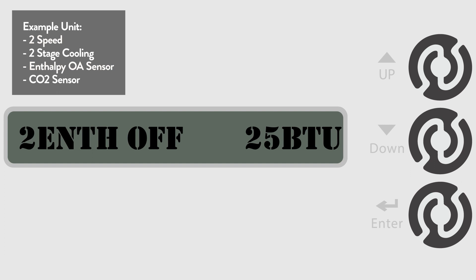The next several screens deal with CO2 sensors. In the 5 configuration state, we told the controller we had a CO2 sensor and we set the sensor voltage. These next adjustments will set the minimum and maximum damper position settings for the controller when not in free cooling. These settings are made by adjusting the voltage to the economizer actuator. Since we have a 2-speed unit, we have a minimum position damper setting for low and high speed, and a maximum position damper setting for low and high speed. The minimum position setting will be used if the space has a low level of occupancy or CO2. The maximum position will be used if the space has a higher level of occupancy.